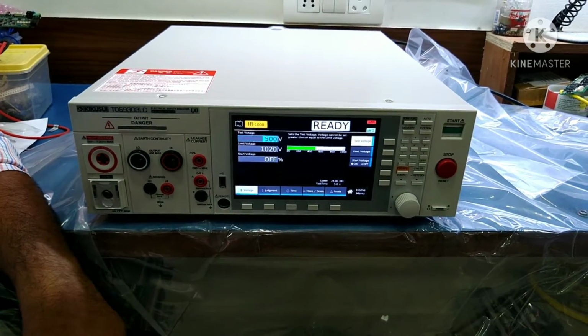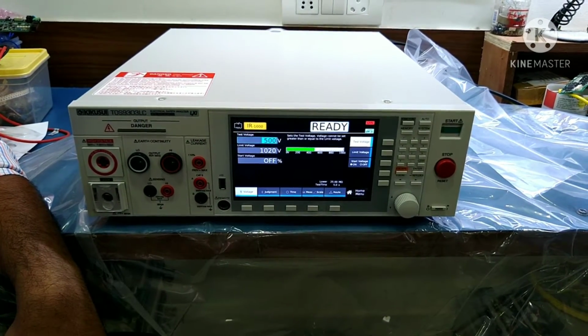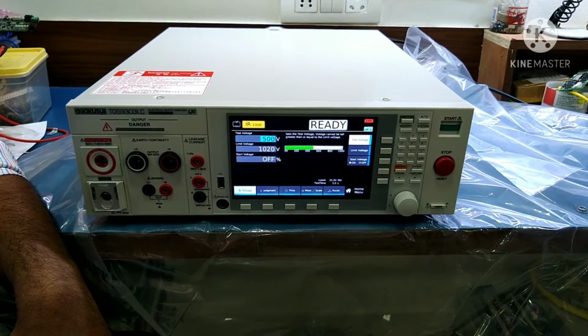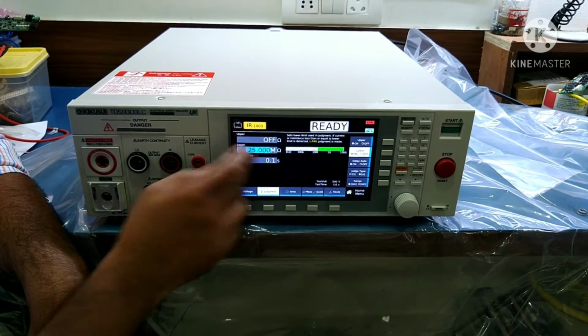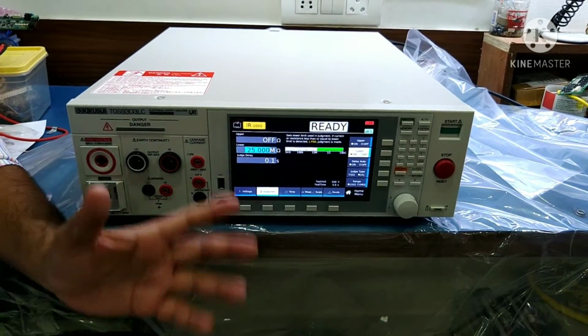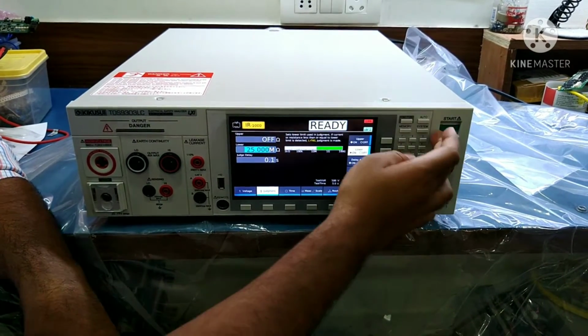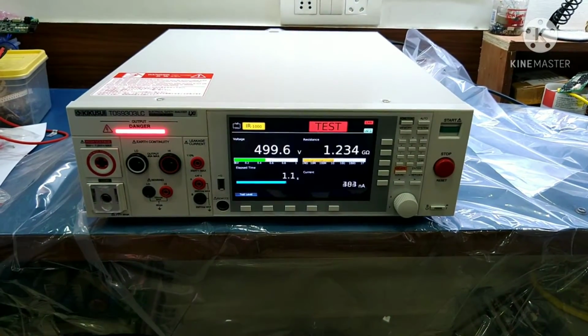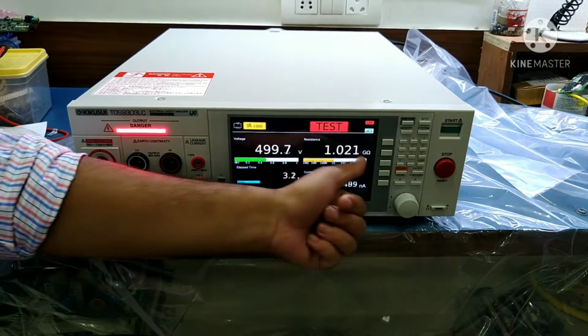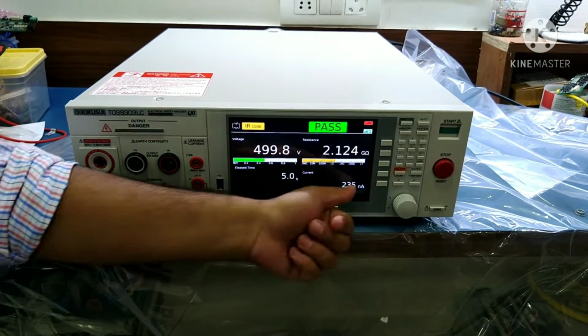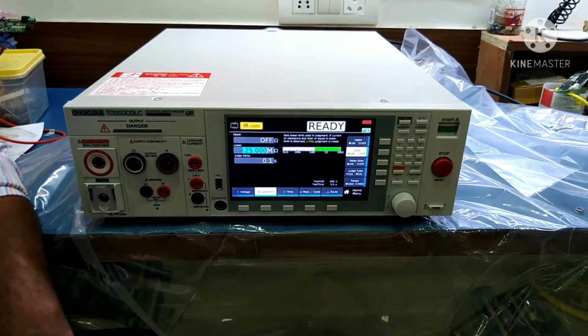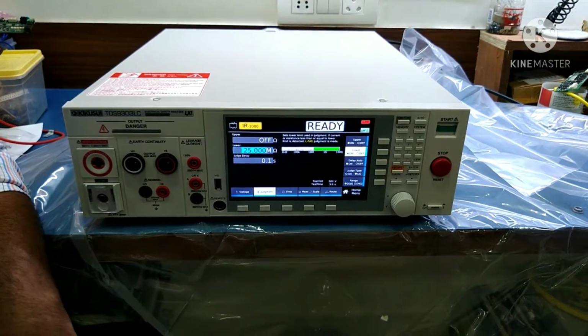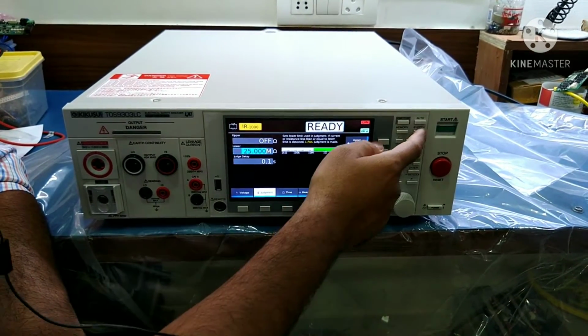In open condition, the resistance will go to infinite. Infinite resistance going up means the lower setting value is only 25 mega ohm, so it will show pass. You can also monitor here the open circuit resistance, the voltage, and the current in the circuitry. So this is the setting for the higher sections. Now I'm going to show the other setting.